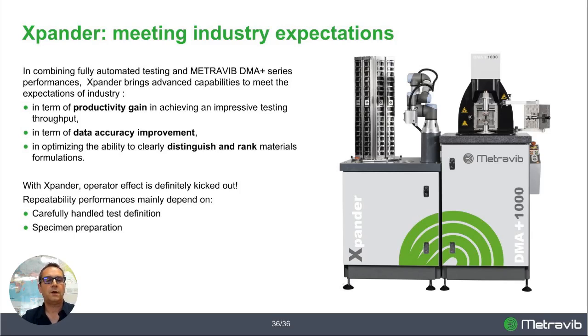So as a conclusion, Xpander is really meeting the industry expectation in terms of productivity gain and data accuracy improvement. This leads to an optimized ability to clearly distinguish and rank the material formulation. It's also a configuration that gives a very satisfying solution regarding the operator effect, because the operator effect is very limited with such an automated DMA configuration. And the repeatability performance mainly depends on the respect and the careful definition of the test condition and the specimen preparation.